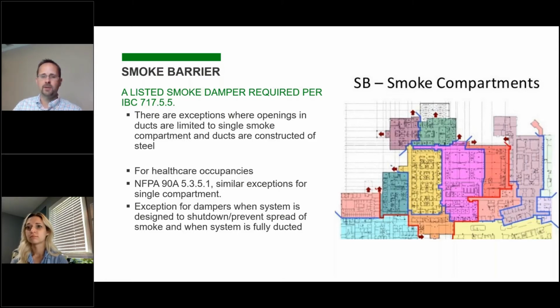And that's a common misconception. Again, I think the 2015 IMC has a section that clarifies that to make it a little bit easier. But in past years, I think there's been some confusion. And so there are some facilities out there that probably have some smoke dampers where they don't really need to. So again, if you're going into an existing facility, you don't necessarily have to copy what they did. Make sure you are designing around the current codes during the project, to minimize the number of dampers that the owner has to maintain and test.